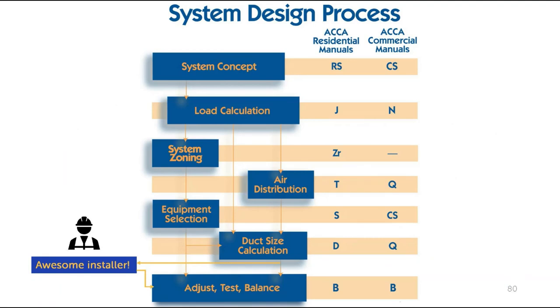Good design ensures good performance, only if you have a great installer. Only in the very best designed and managed projects are field changes not needed. Most projects have some unforeseen or unplanned issue that necessitates field modifications. A plumbing line here, a surprise framing over there. These are common examples. Providing open and reliable communication between the installer and designer is imperative to ensuring field improvisation doesn't negatively impact performance. The graphic on the slide shows the many manuals available from the Air Conditioning Contractors Association for sizing, designing, and testing heating, cooling, and ventilation systems.